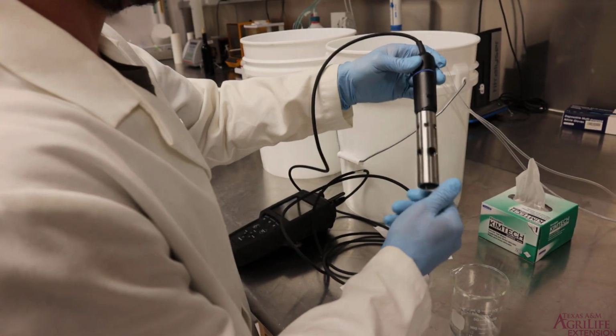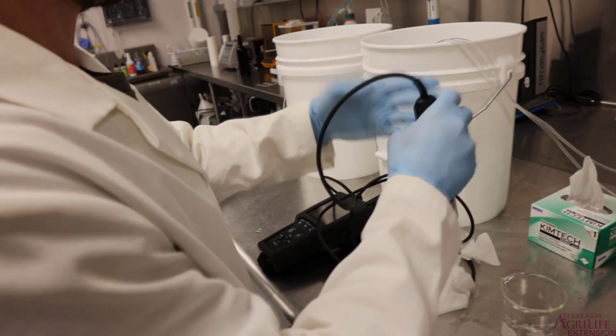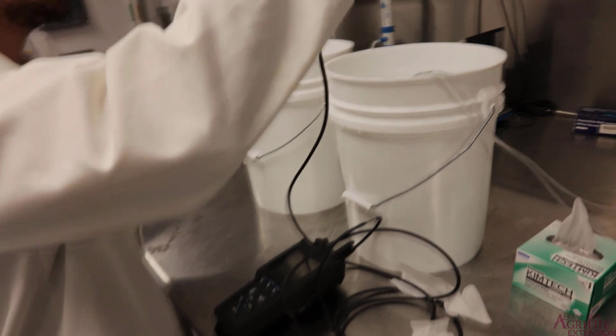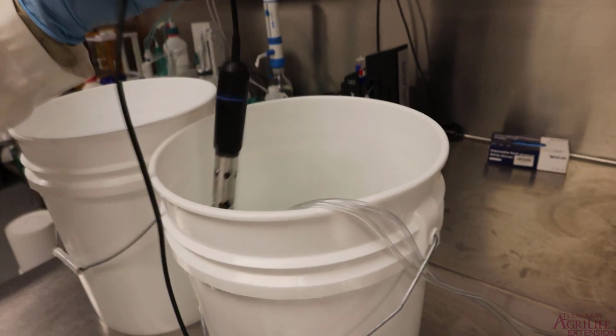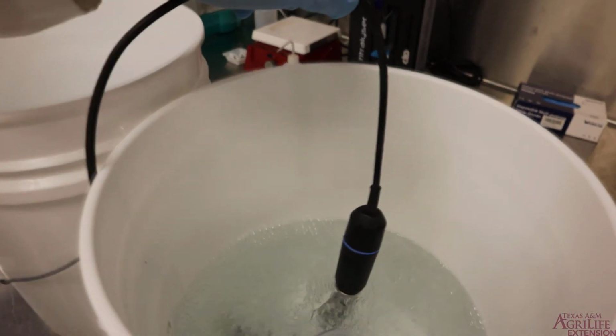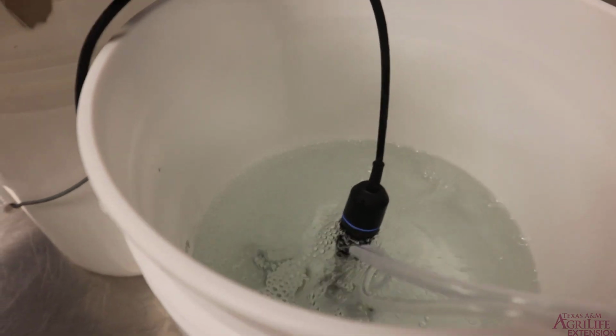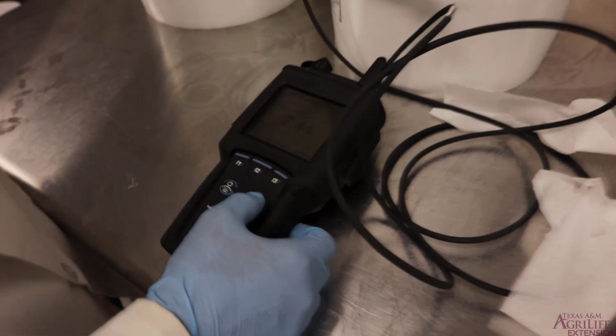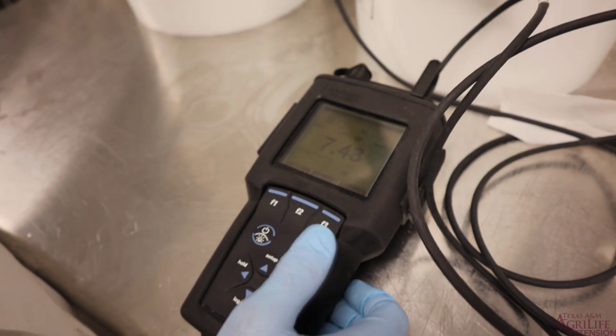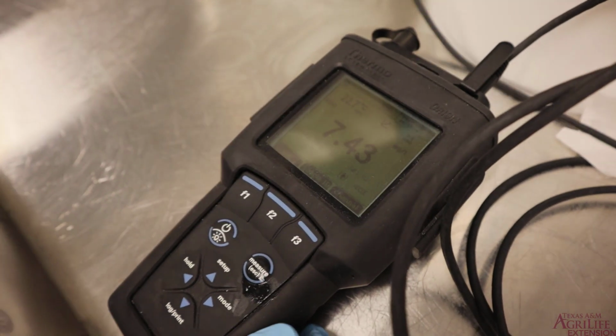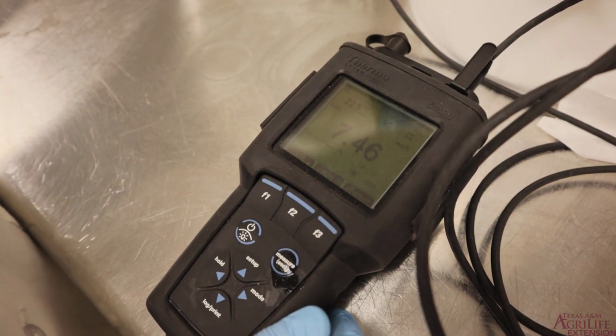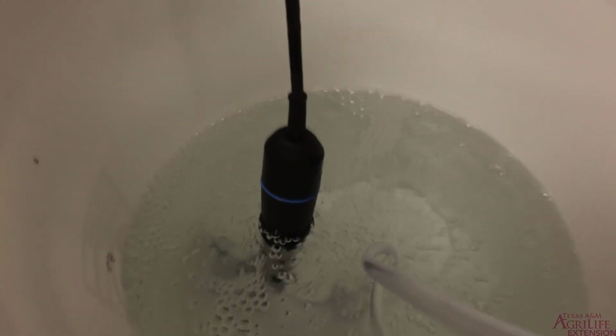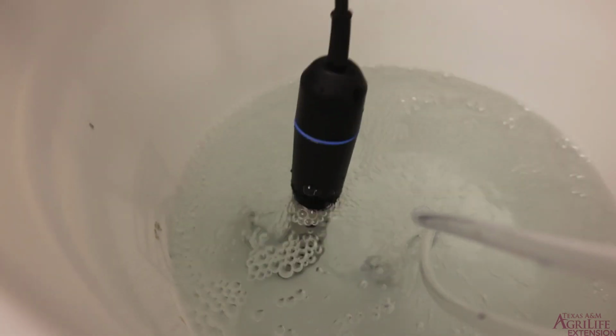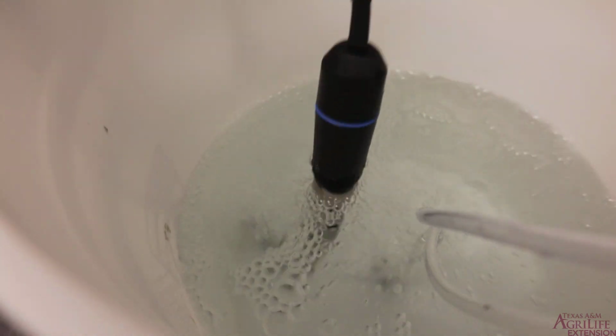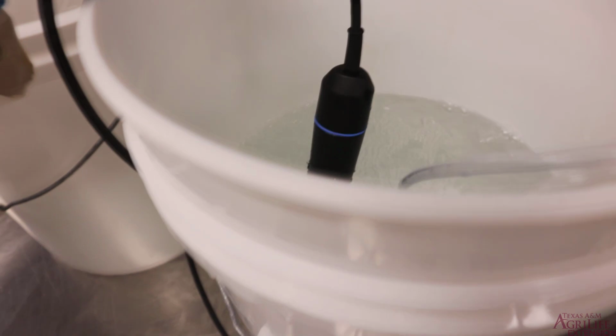And then if we're going to the tank next door to us, we should be right there, and we can go ahead and drop this in for our next tank, just like we did with the first tank. Drop that in there. Once it's in the tank, we will go ahead and hit the measure button. And we will bob our probe up and down just like we did on the previous tank. So, a little side note with this, if you are doing this as a cellar application, remember this will be done at the tank top.